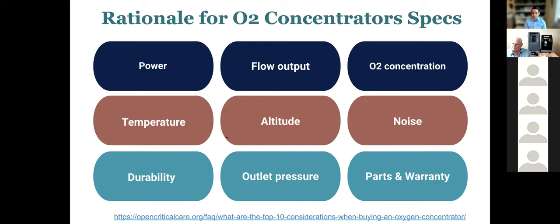Temperature, altitude, just the operating environment is important. So by WHO specs, these devices should be able to maintain that max oxygen concentration at the max flow rate, or excuse me, they should maintain an oxygen concentration of greater than 82% at the max flow rate in a harsh environment. So at a temperature of 40 degrees, a relative humidity of 95%, et cetera. So keeping an eye on that's important.